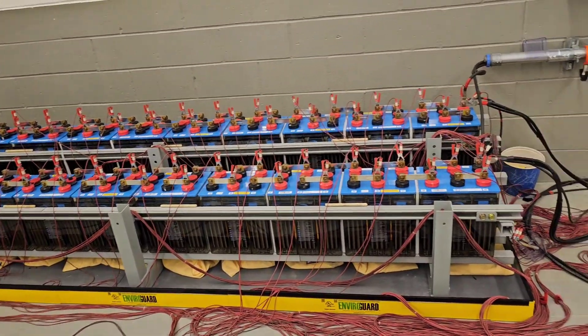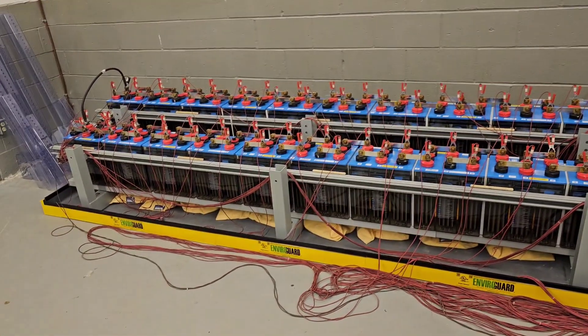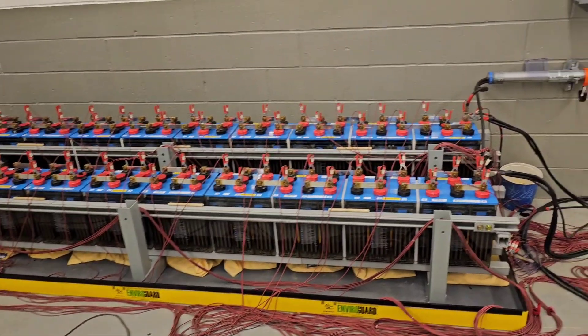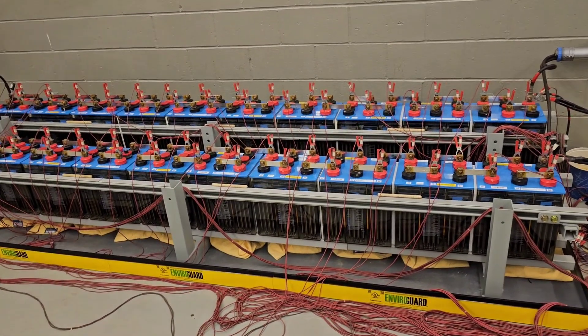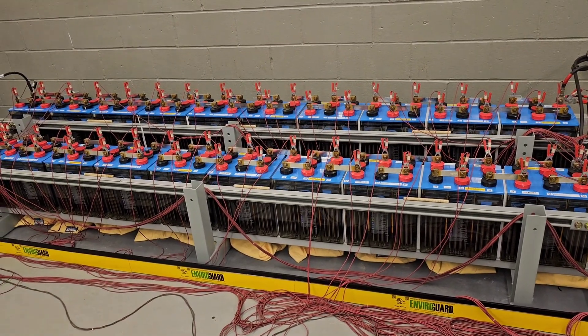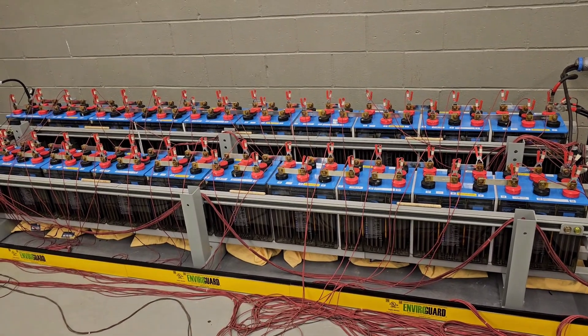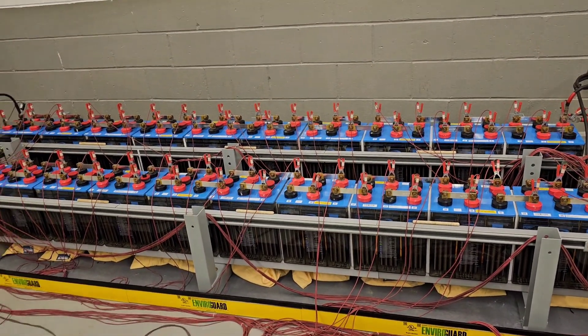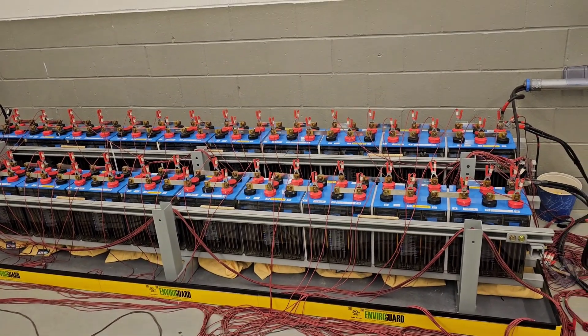all these critical systems will continue to operate on these batteries. To make sure they function the way they should, we test them — checking that the acid is at the correct specific gravity, the internal resistance, and the connections between the cells. But once in a while we have to really put the battery to a test.